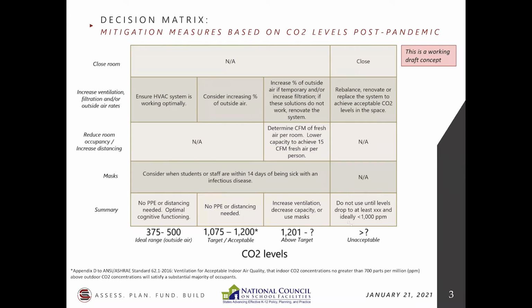The other thing is, what do you do if you've got limited capacity, limited ability to bring in outdoor air, or it's not bringing in outdoor air? You could bring in air cleaners. Now, in the age of COVID, we're looking at aerosols, and we consider those particulate of sorts, such that air cleaners will address that. Air cleaners are not a surrogate; they are not a replacement for ventilation. But when it comes to removing viral particles or agglomerates thereof, which typically is really what we have, you don't have viruses just floating around, air cleaners can do a decent job of reducing that. So that's an option that could be looked to.